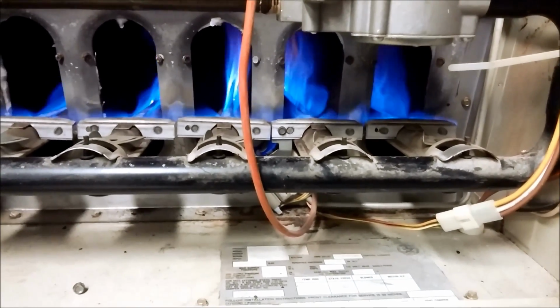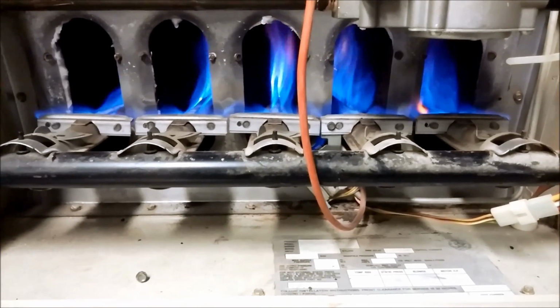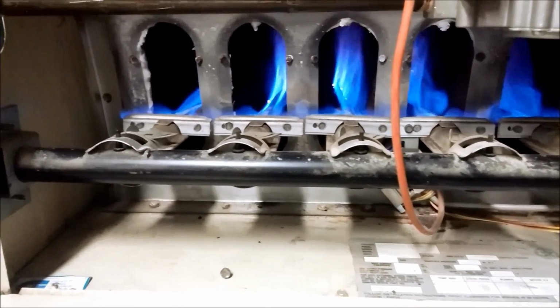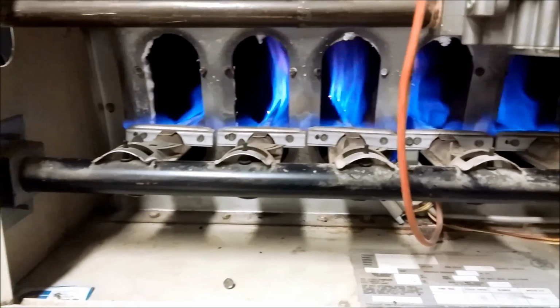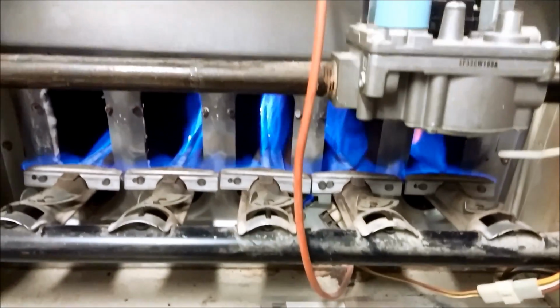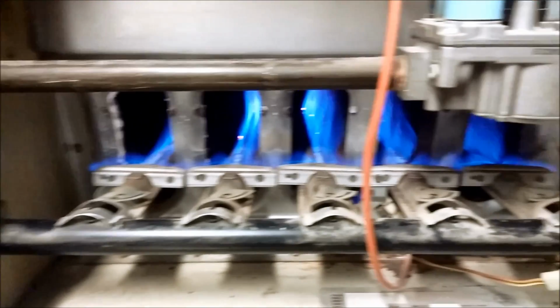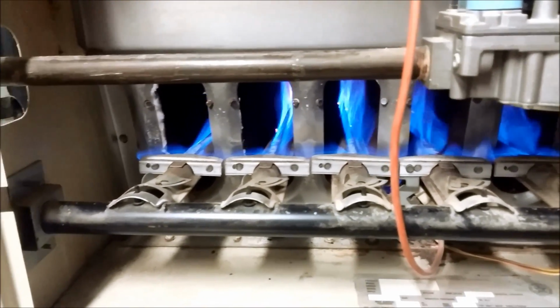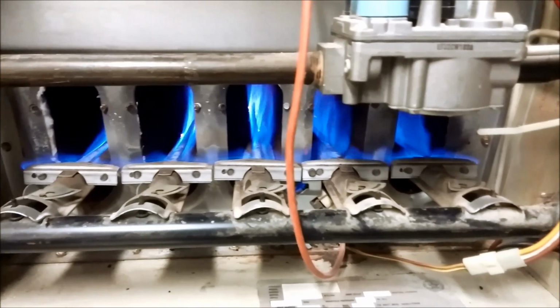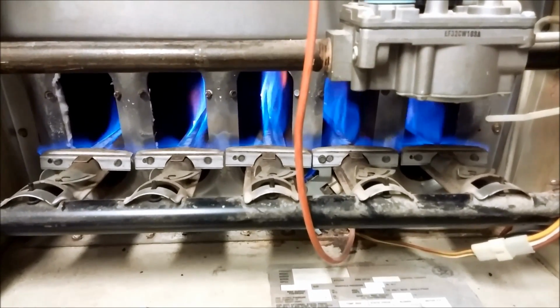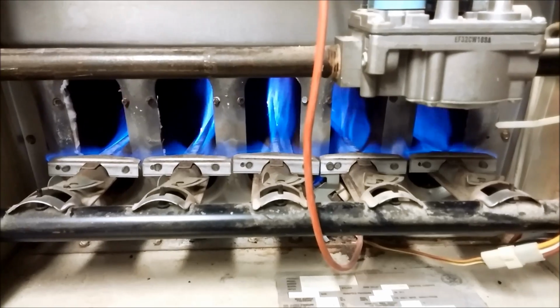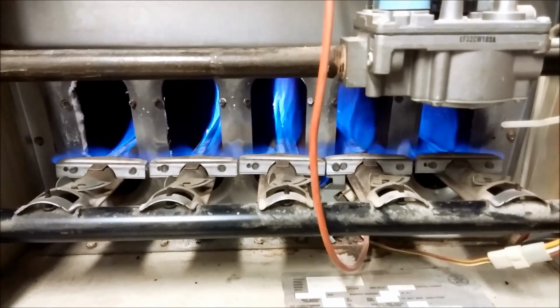So this just goes to prove that if you have a cracked heat exchanger, there's no guaranteed flame rollout. Nothing. Runs like a champ. But I got gaping cracks in the heat exchanger. Alright, let me finish this one up. We just got done with that call. And those are the kind of things that just take your breath away.